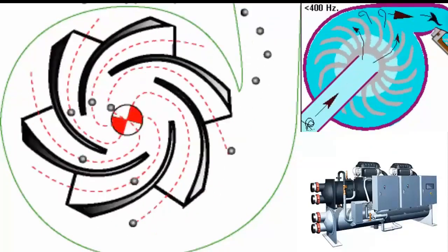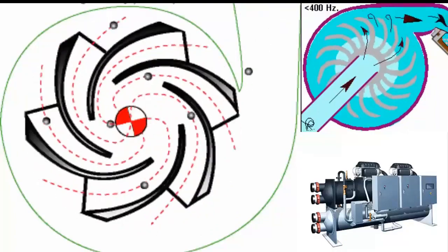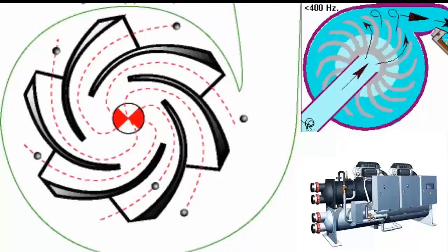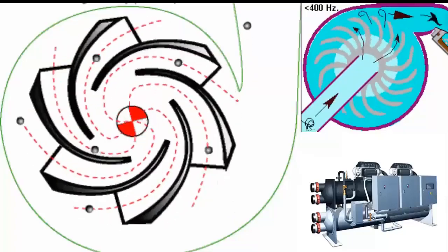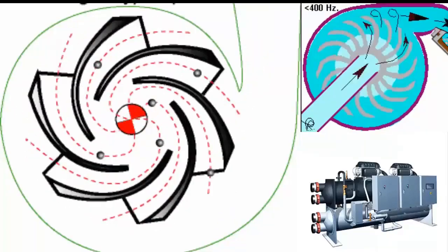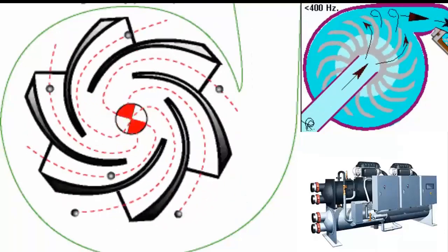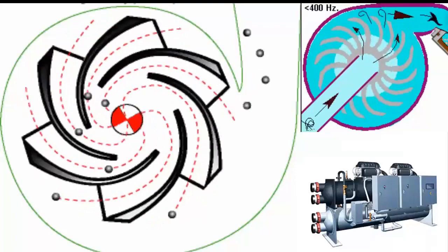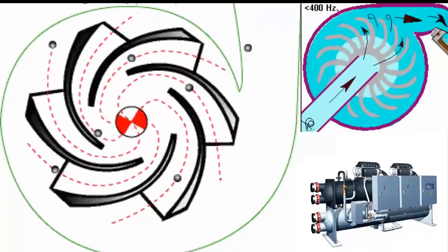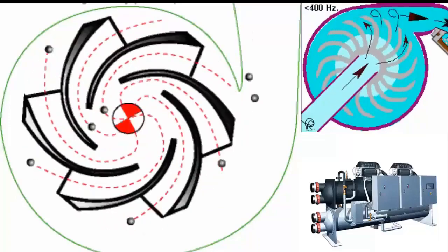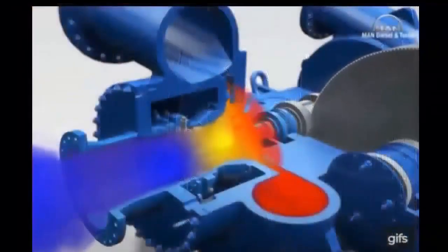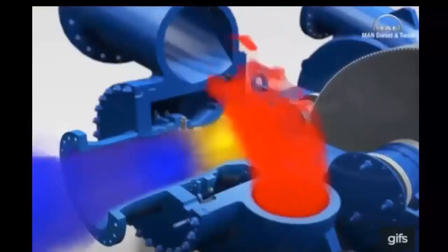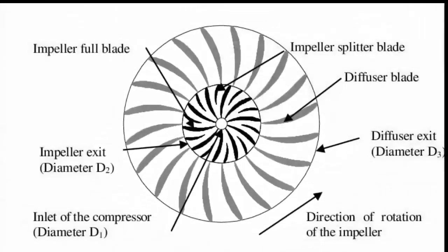The condensation in the condenser is particularly important because it will allow us to carry out the cycle. It goes from liquid to vapor in the evaporator and from vapor to liquid in the condenser to convert the machine into a constant cycle. So how is this pressure going to be achieved? First we pass the electrical energy from the motor to the coolant in the form of velocity. Now since the refrigerant already has speed from the impellers, we are going to convert that speed into pressure. It's kind of like having a gearbox - we already have third gear but now we need to go up, so we're going to start downshifting to second gear. That's what we're doing with the coolant, playing with the changes.